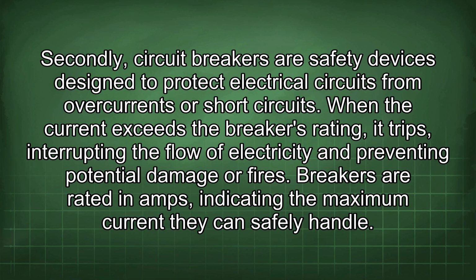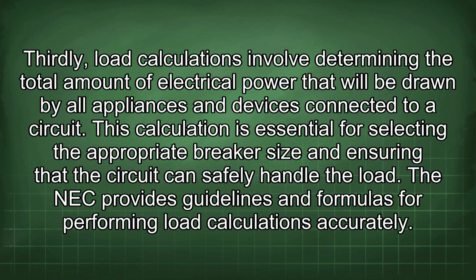Secondly, circuit breakers are safety devices designed to protect electrical circuits from overcurrents or short circuits. When the current exceeds the breaker's rating, it trips, interrupting the flow of electricity and preventing potential damage or fires. Breakers are rated in amps, indicating the maximum current they can safely handle. Thirdly, load calculations involve determining the total amount of electrical power that will be drawn by all appliances and devices connected to a circuit. This calculation is essential for selecting the appropriate breaker size and ensuring that the circuit can safely handle the load. The NEC provides guidelines and formulas for performing load calculations accurately.